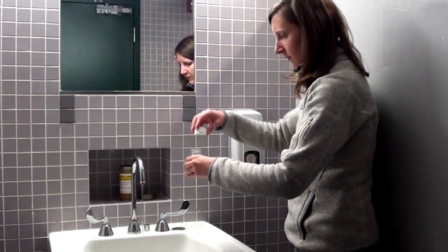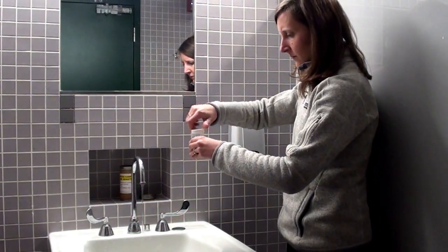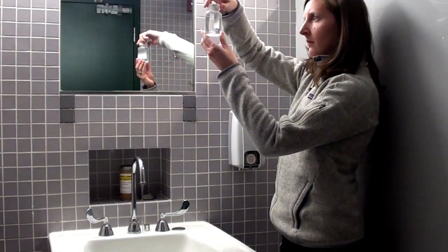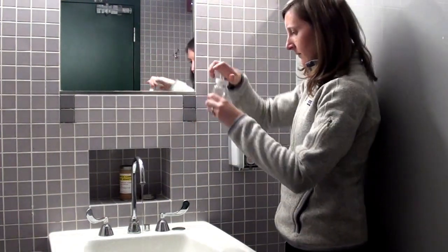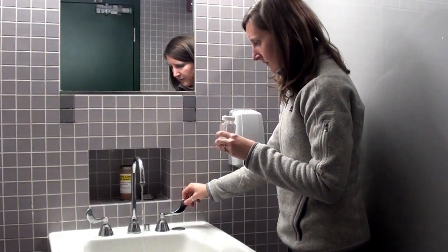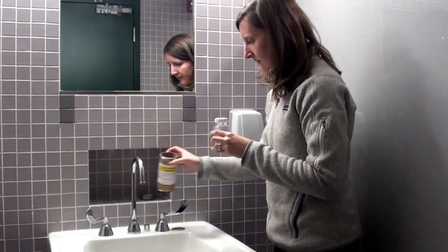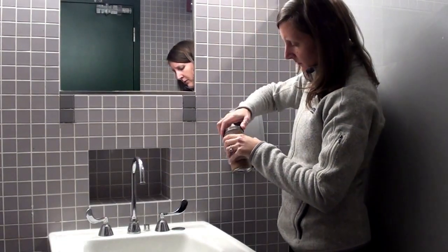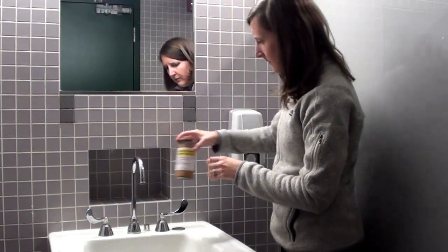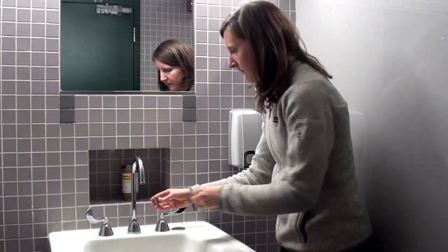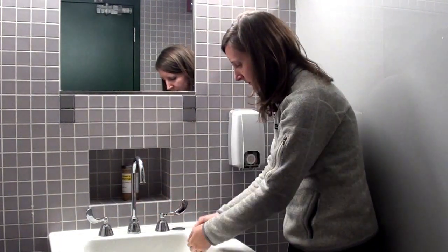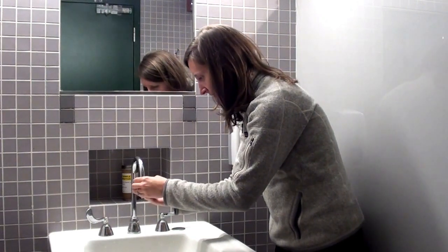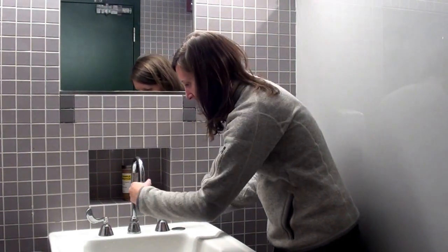Issues such as using an unclean sample tap, a tap where the aerator wasn't or can't be removed, failure to flush the tap adequately prior to sampling, or other sampling errors can result in positive samples. Additionally, anything coming in contact with the sample bottle other than the water being tested can impact the results. This would include putting the cap in your pocket, on a counter, or on the ground while taking the sample, or touching the inside of the cap or bottle.